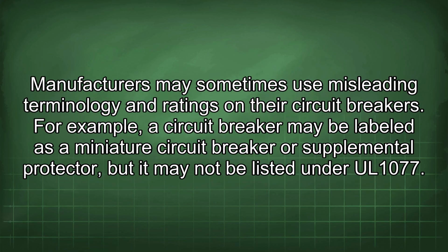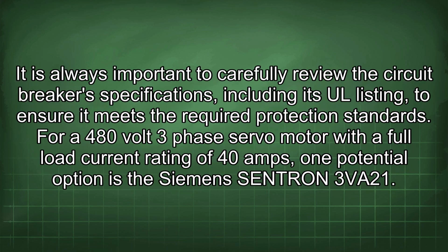Manufacturers may sometimes use misleading terminology and ratings on their circuit breakers. For example, a circuit breaker may be labeled as a miniature circuit breaker or supplemental protector, but it may not be listed under UL 1077. It is always important to carefully review the circuit breaker's specifications, including its UL listing, to ensure it meets the required protection standards.